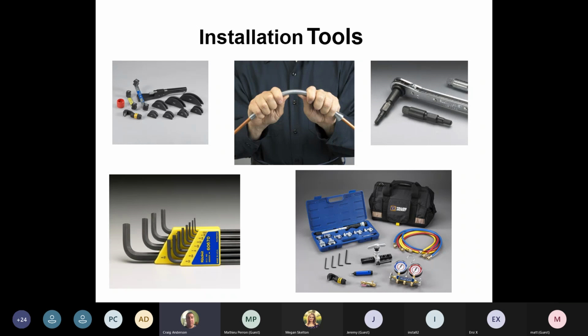Sometimes it gets in deep enough. It all depends on the mold of that valve. If it doesn't get in deep enough, there's a 75% chance that you're going to strip that valve. Get in there with a standard Allen key, get your first crank, then get your service valve in there, and then open up the rest. It's going to save you a lot of headache down the road. If you strip that service valve, it ain't fun to change.